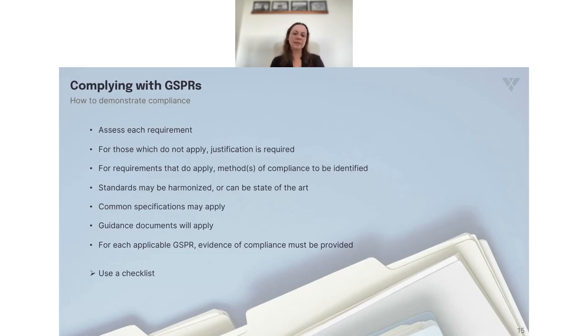You can use standards. Some of these may be what's called harmonized with the MDR. Now, there are very few at this point in time that are harmonized, so it tends to be more popular to go with those that are state of the art, which tend to be the latest possible version. Note that common specifications may apply. These are essentially something that the Commission write to address areas for which there are no standards. So they might decide that for certain types of devices or categories, they may need to set specific requirements out.